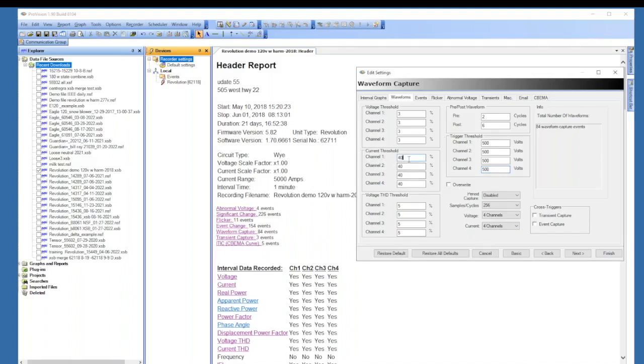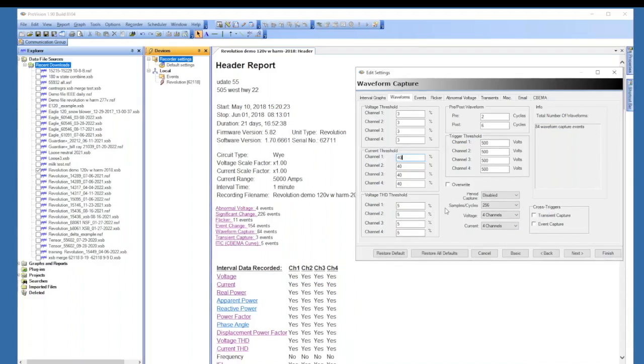Your current trigger is based on a percentage, but it's also based on what you set your current range to be. So if it was 5,000 amps, then it'd be 40% of 5,000 amps. So you would have to have inrush of 2,000 amps from one cycle to the next in order to trigger a waveform capture. And if you don't have that, then you want to go ahead and adjust that. So 40% of 1,000 if you set it for the 1,000 amp current range. And then the Revolution will trigger on voltage total harmonic distortion. 5% is pretty much the IEEE limit, the standard limit.